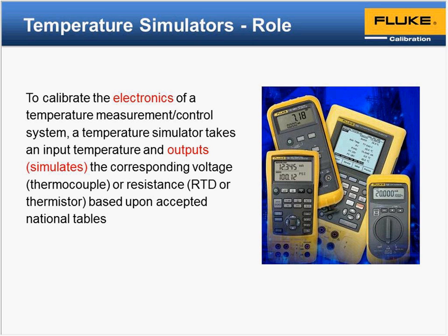The other thing to consider with the simulator's role is that it can also output other things besides just the RTD. We're notorious for having a wide range of thermocouples that you can select, and in that case you would be simulating a millivoltage, and then in some we also simulate thermistors. The thing to note about thermistors is that it's a much higher resistance range. Most are nominally about 25 C, about 10k ohms. And these are all typically based off of national tables, like the DIN class, or ASTM, or the graphs for the thermocouple.